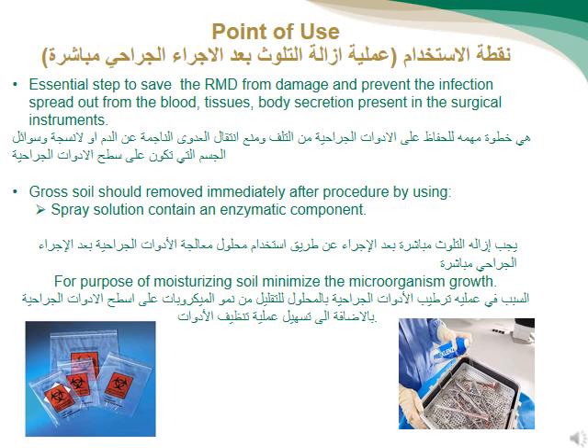Gross soil should be removed immediately after the procedure by using a spray solution containing an enzymatic component, or by wiping with pre-clean medical wipes, to moisturize the soil and prevent rust and corrosion if dried on the device surface, and to minimize microorganism growth. يتم معالجة الآلات الجراحية الملوثة بمحلول إنزيمي عن طريق الرش أو المسح لتسهيل التنظيف وضمان إبقائها رطبة، ومنع تجلط الملوثات التي قد تسبب الصدأ أو التآكل، والتقليل من نمو الميكروبات وتفكيك طبقة البايوفيلم.